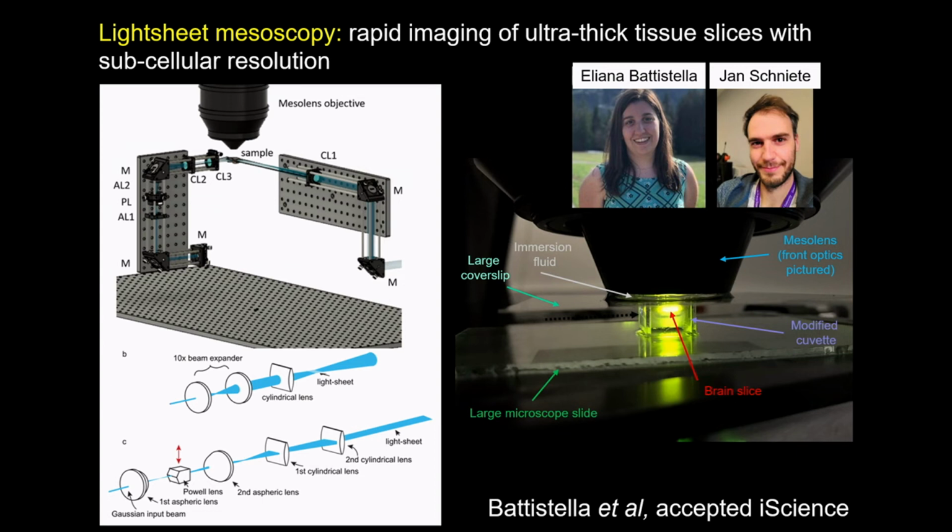That's with a pixel dwell time of 1/4 of a microsecond. And we can use that short pixel dwell time because the high NA, the Mesolens, gives us really high detection efficiency and optical throughput. Then for our Z series, we need to think about the number of Z planes and so on. So that's why it can take us a week to image one very large clarified volumetric specimen. So invariably we were presenting these data and people are sending us samples, and the throughput's agonisingly slow.